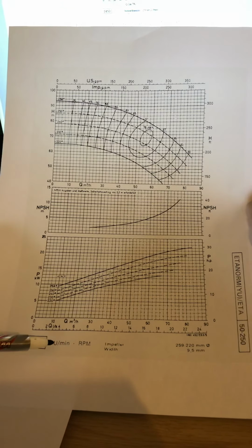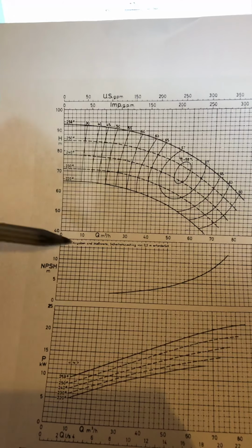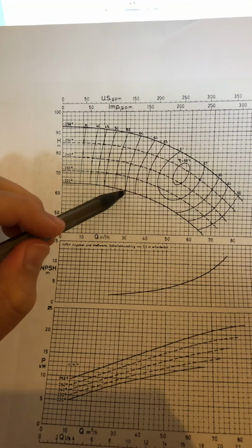So a couple of things that you need to know. If I ask you to give me the cutoff pressure, or the cutoff distance, sorry, in Afrikaans, the afsluitpunt, you'll take that 30 and 220 and you follow this curve right back to there. So in this case, the cutoff distance is that point right there where the curve crosses the y-axis. The next one is pump head at duty point, or pompdruk by dienspunt, and it is that point where this flow rate and the impeller curve cross. So that is the pump head at duty point. Just so as not to get confused, this is the cutoff distance and this is the pump head at duty point.